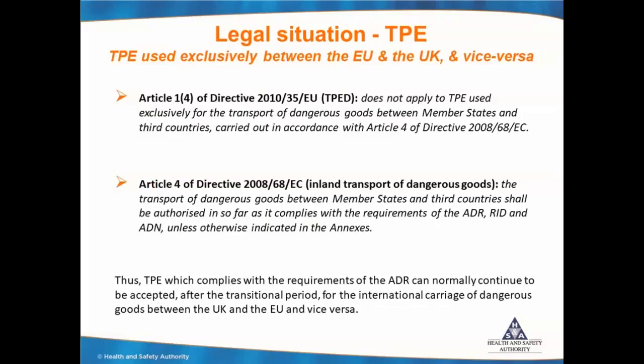So under Article 1.4 of TPED, it says that it does not apply to TPE used exclusively for the transport of dangerous goods between member states and third countries if it's carried out in accordance with Article 4 of Directive 2008/68/EC. And Article 4 of that directive on the inland transport of dangerous goods says the transport of dangerous goods between member states and third countries shall be authorised insofar as it complies with the requirements of the ADR, RID and ADN, unless otherwise indicated in the annexes.